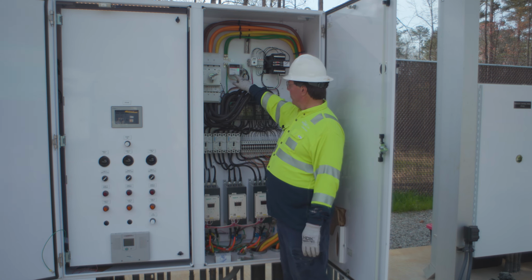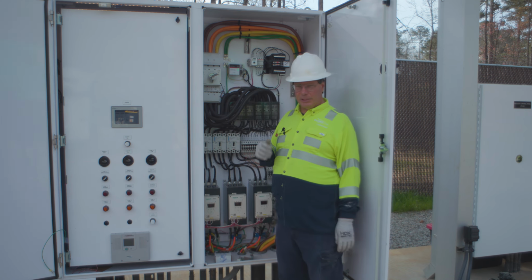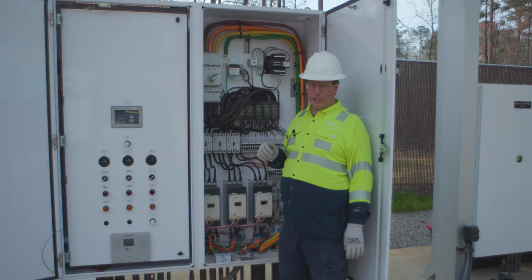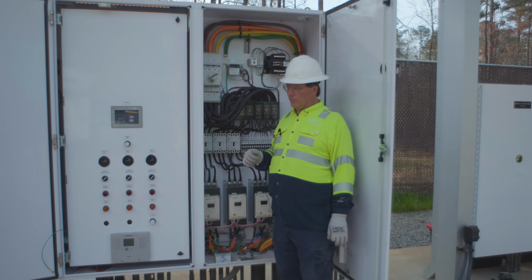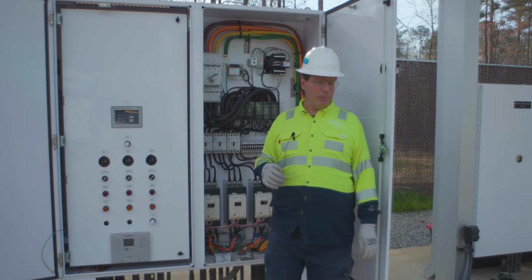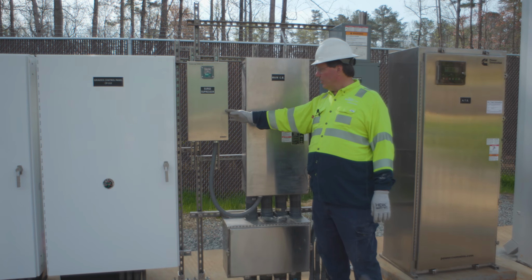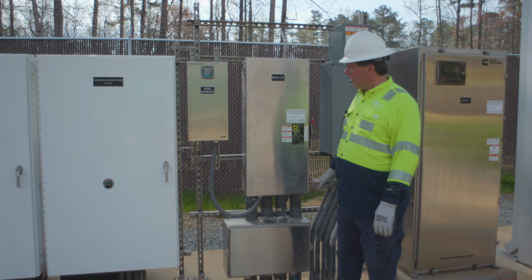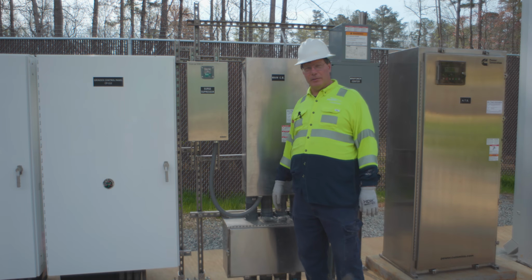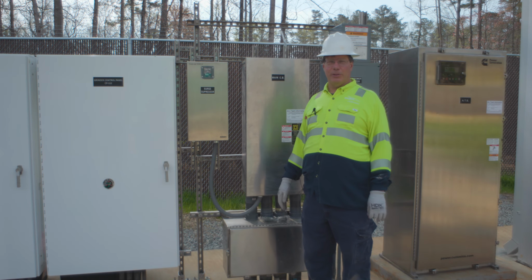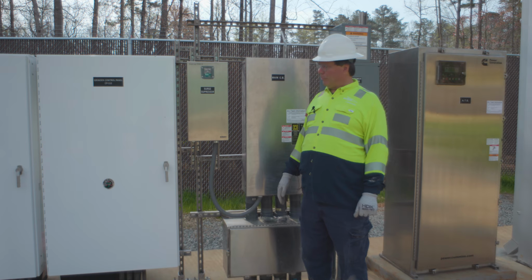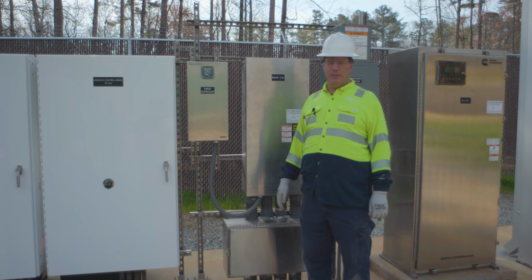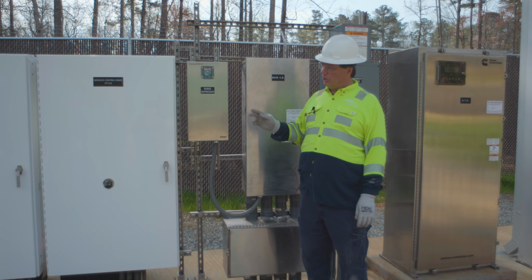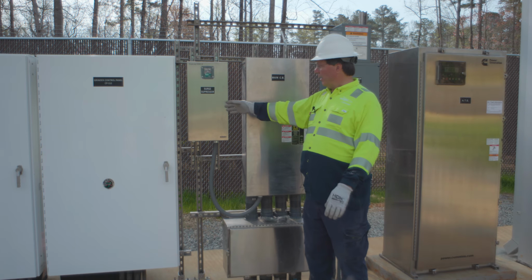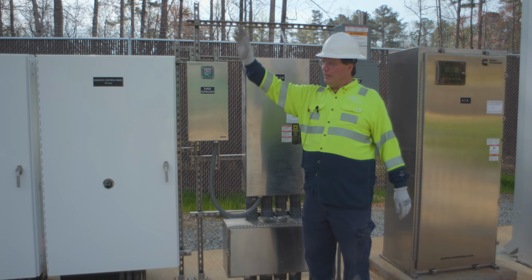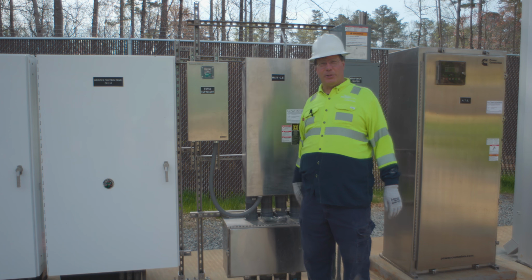This is our surge protector. The surge protector for this panel only. There's a separate surge protector for the station, which is not supplied. Well, actually it is supplied by us. So the surge suppressor is located right next to the main circuit breaker. And what it does is it gets rid of all the high voltage transients up the line and protects all the equipment at the station. That smaller surge suppressor is just for that cabinet. So this one actually protects everything here, and then there's another one in the cabinet for the controls for that cabinet.